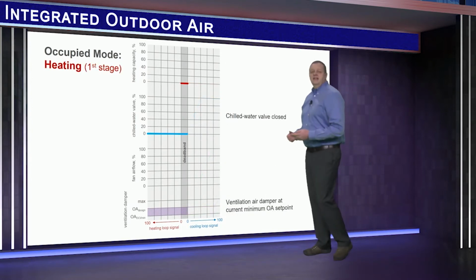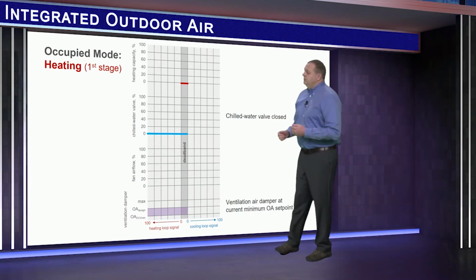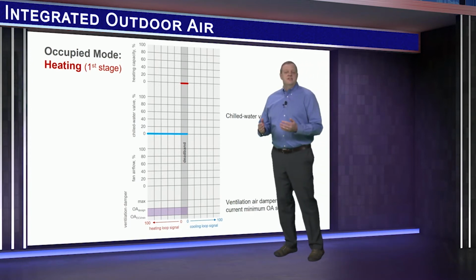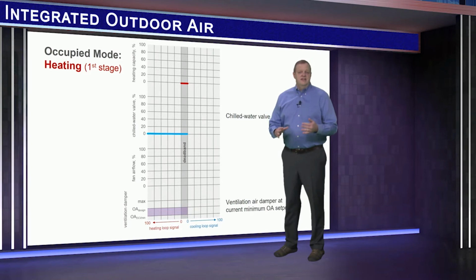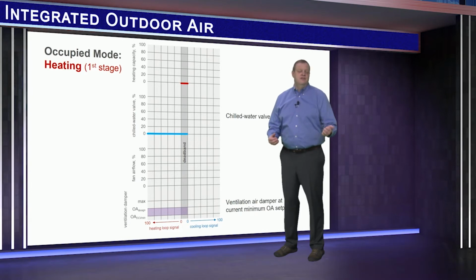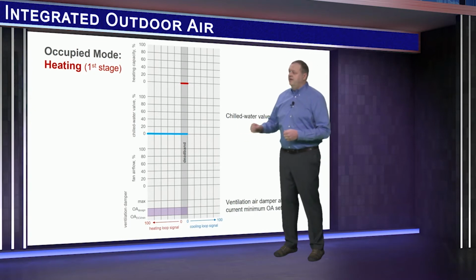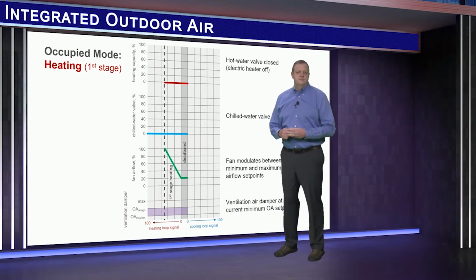Now let's move to the heating operation. When the temperature in the zone drops to its heating set point, let's say 70 degrees, the controller attempts to maintain zone temperature at this set point by modulating the terminal fan speed and the hot water coil or electric heater. In this case, the chill water valve now remains closed.